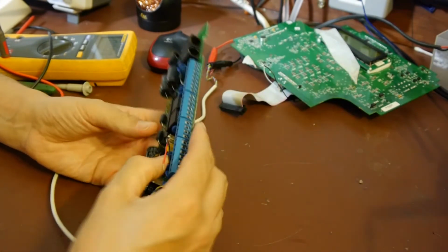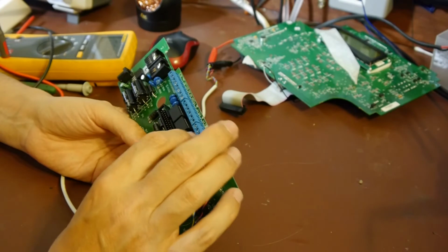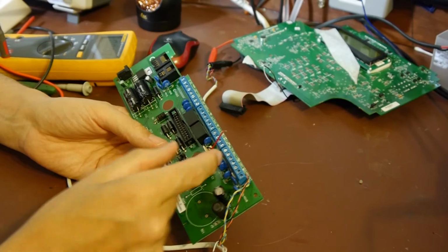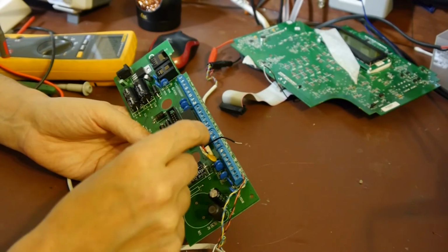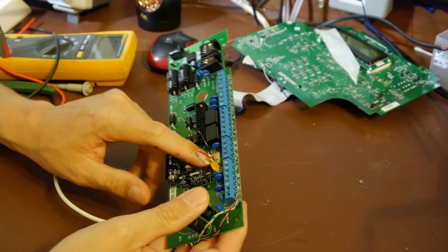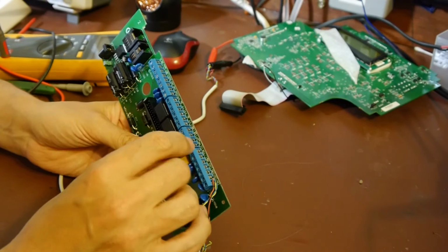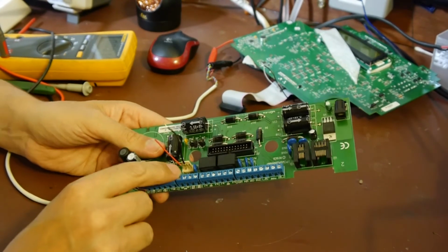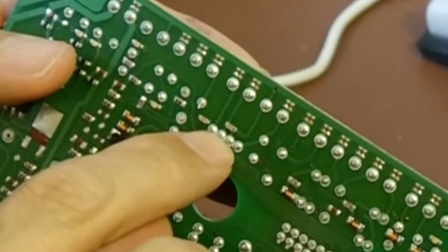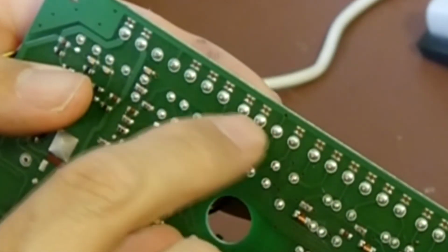We've then got what they call a bus connector here, which I'm thinking is where we were connecting the 485 to previously. I just soldered a couple of wires onto it. In fact, maybe we can see that. So we've got a connector that says bus here, but there's also a bus connection on these 4 screw terminals. So do those try? Oh yeah, okay. So it looks like you can plug in that 485 network either on this little 4-way header, or you can equally well just wire to this connector block here, because you can see that the wires are coming from the 4-way header going to the terminal strip above.